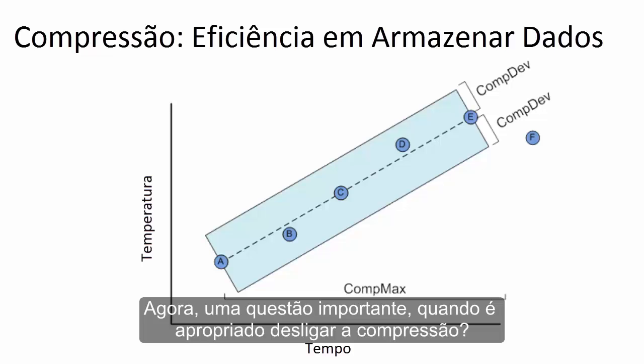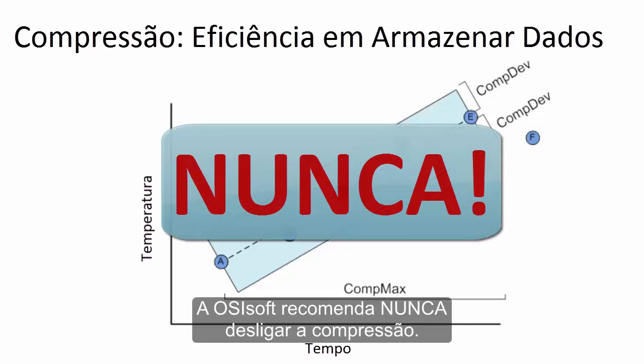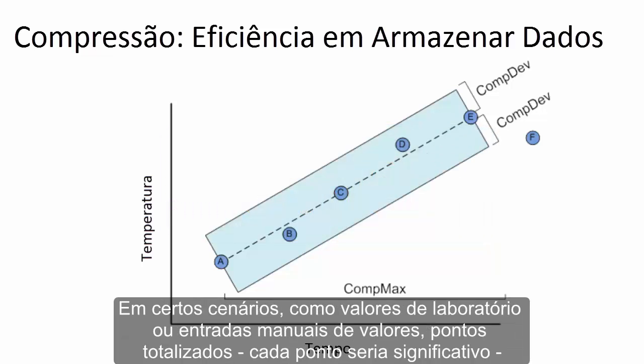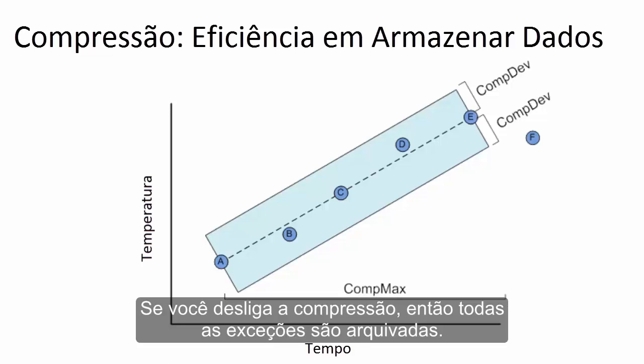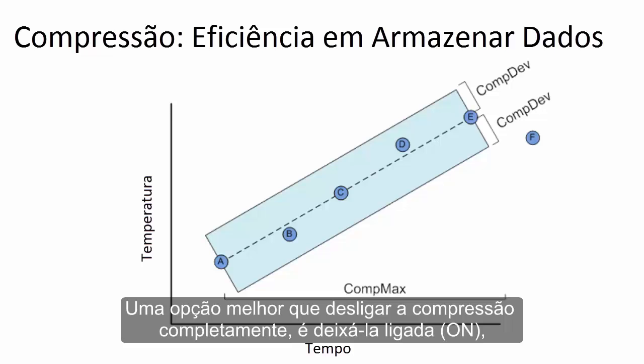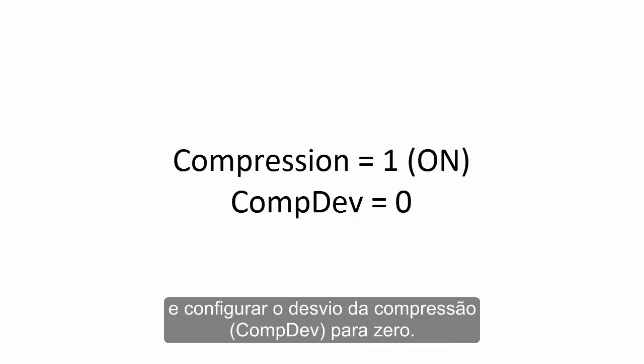This raises a very important question: when is it appropriate to turn off compression? OSIsoft generally recommends never turning off compression, but there might be a few scenarios such as lab values or manually entered values, totalized points where every point is significant, or governmental requirements where you need to archive all collected data. If you turn off compression, then all exceptions are archived. A suggested better option instead of turning compression off completely is to set compression to ON but set compression deviation to 0.